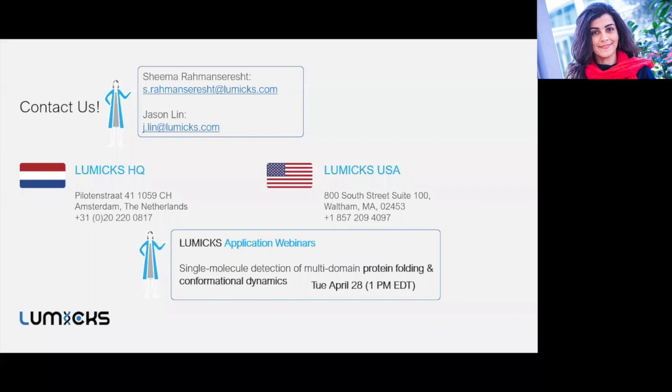Yeah, indeed. I said that they use 600 piconewton. With C-Trap, you can apply forces from 0.1 piconewton to 1,000 piconewton. This all depends on the laser power that you're using, and also the size of the bead. All of those affect how much force you can apply.